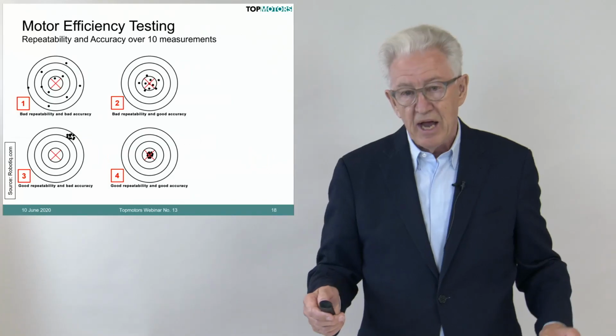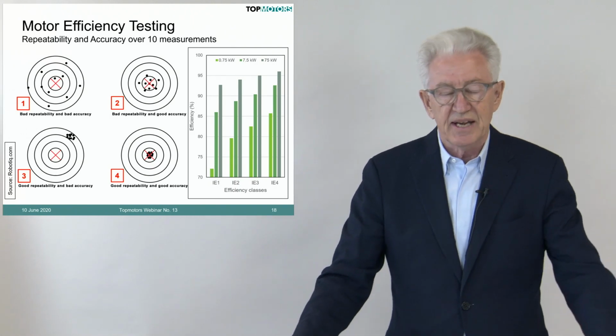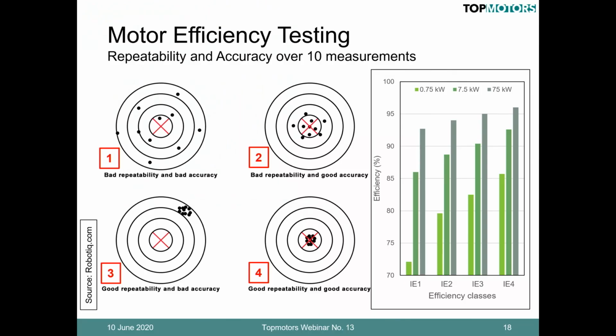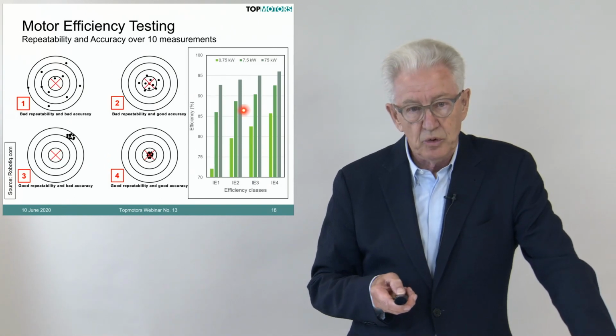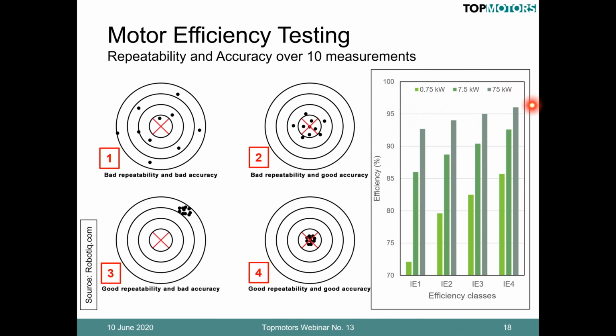Why is this important? I show you what the efficiency classes and the efficiencies are for a relatively bad today, IE1 standard motor, IE2 high efficient motor, IE3 premium efficient motor, and IE4 super premium efficient motor. Now, when you look at these bars, they show the efficiency on the left, the vertical scale. You have the efficiency in percentage. I chose to show 3 types of motor. A very small one, 0.75 kilowatt, 1 horsepower. That's a light green. One middle size, very often used, 7.5 kilowatt. That's the middle green. And this large size, 75 kilowatt, is on the right side.